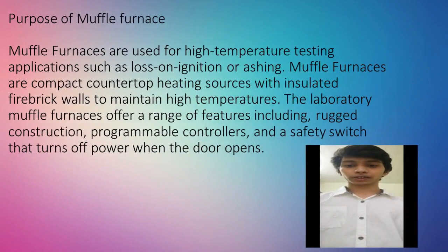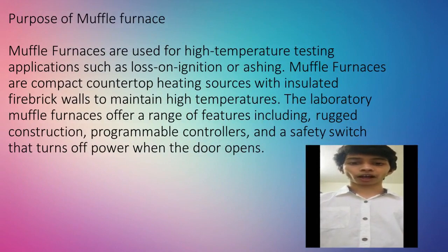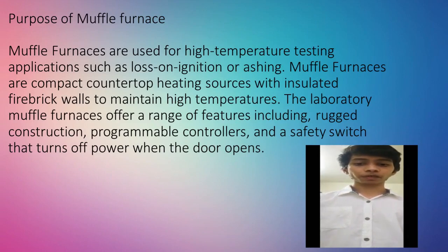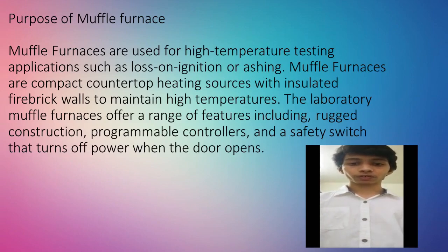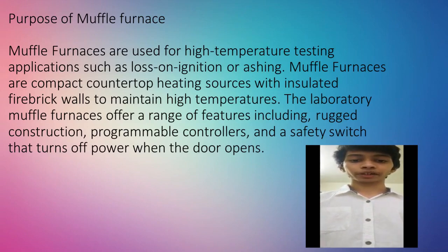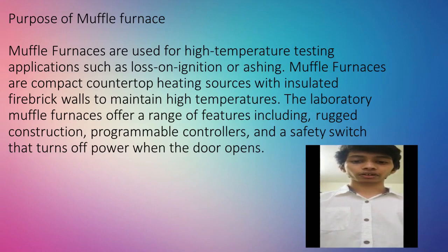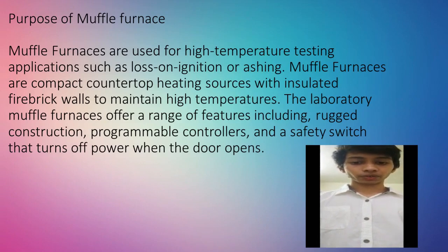Purpose of muffle furnace: muffle furnaces are used for high-temperature testing applications such as loss on ignition or ashing. Muffle furnaces are compact countertop heating sources with insulated firebrick walls to maintain high temperature. The laboratory muffle furnace offers a range of features including robust construction, programmable controllers, and a safety switch that turns off power when the door opens.